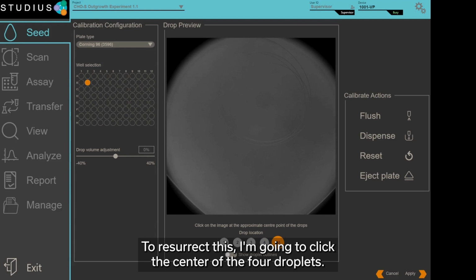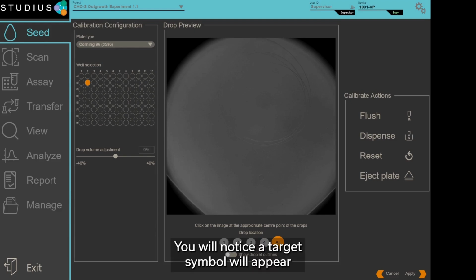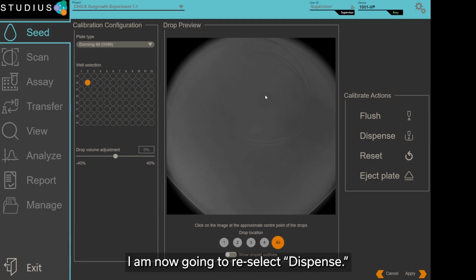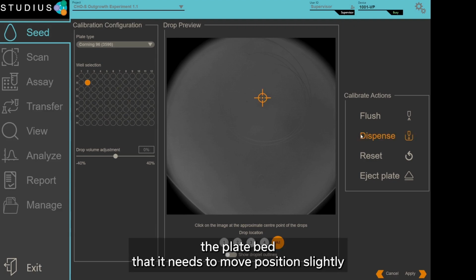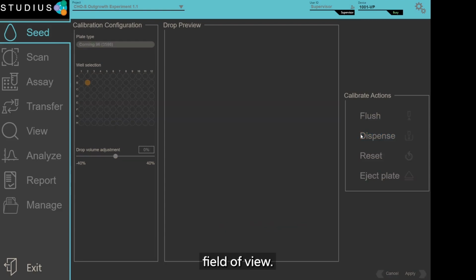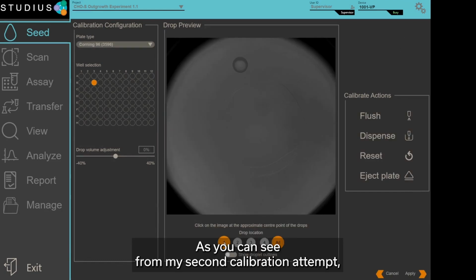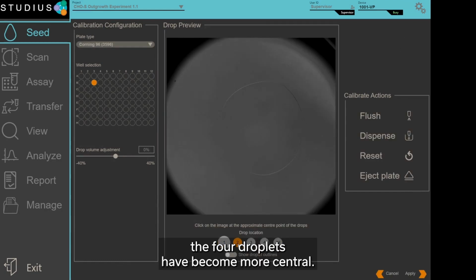To correct this, I'm going to click the center of the 4 droplets. You will notice a target symbol will appear on the location where I have just selected. I am now going to reselect Dispense. The STUDIUS software will inform the plate bed that it needs to move position slightly so that the location of the droplets dispensed are within the camera's field of view. As you can see from my second calibration attempt, the 4 droplets have become more central.